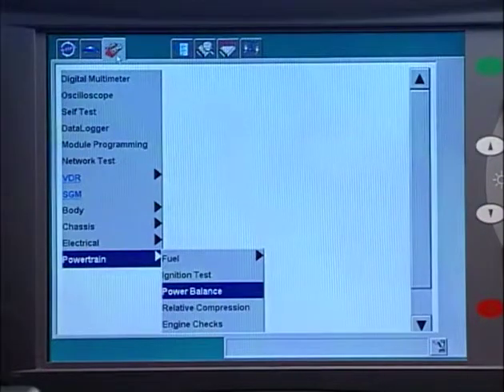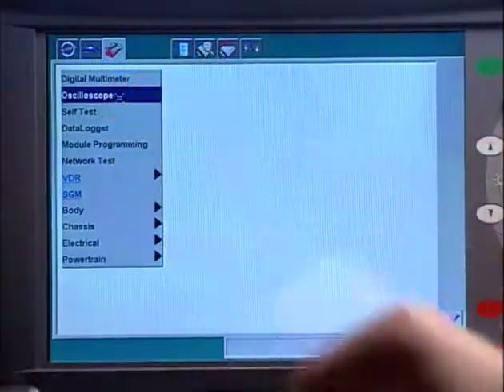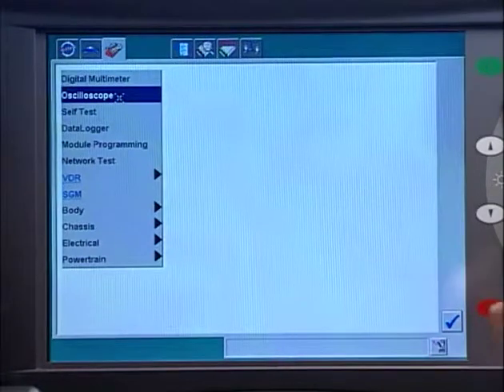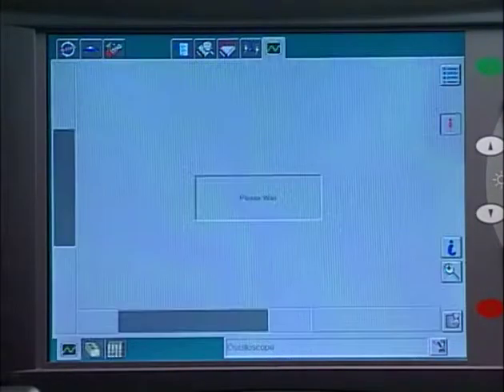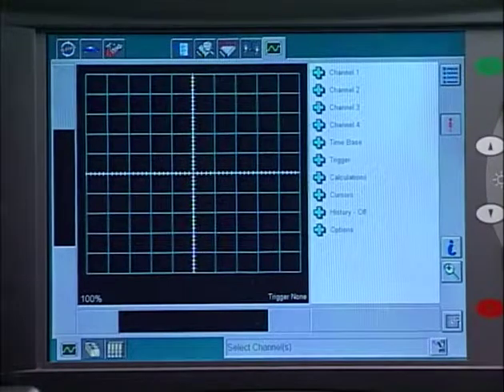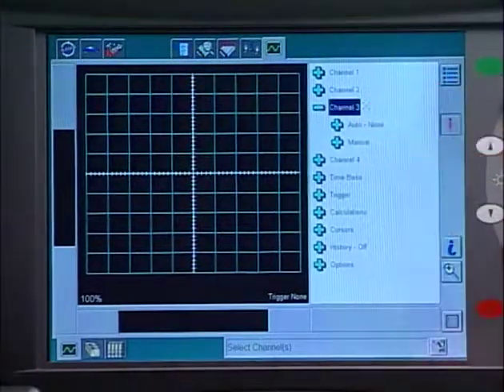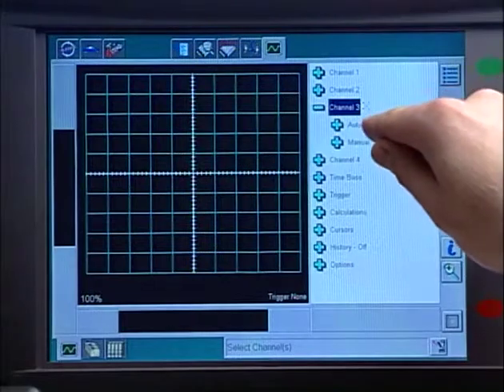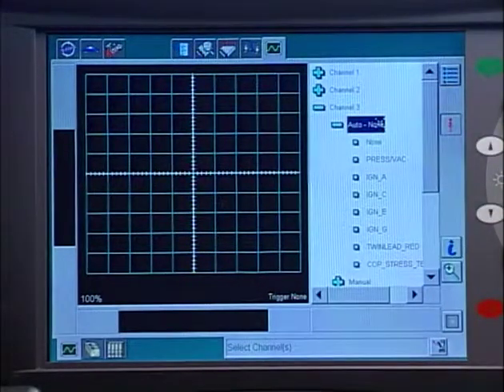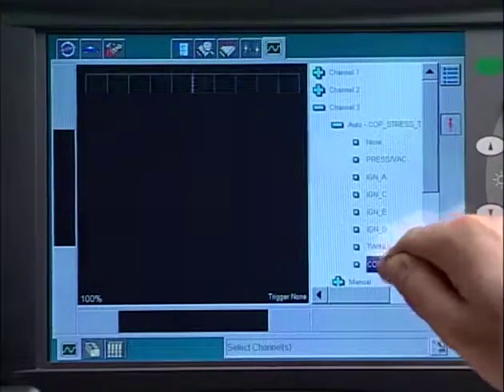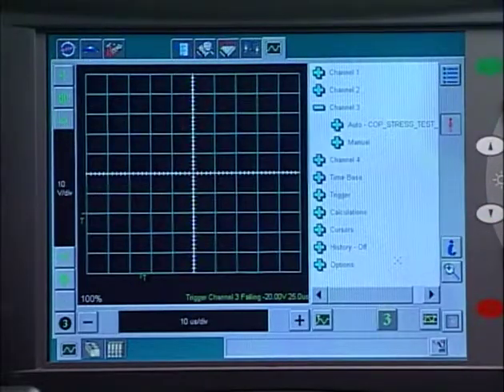From the main screen, select the toolbox on the top left. A new menu will appear. Select Oscilloscope, then select the tick button. The oscilloscope will then open. Select Channel 3. A drop-down menu will open with Auto None and Manual. Select Auto None, and another drop-down menu will appear. At the bottom of the menu is COP stress test. Select this, and the WDS will automatically configure the oscilloscope.